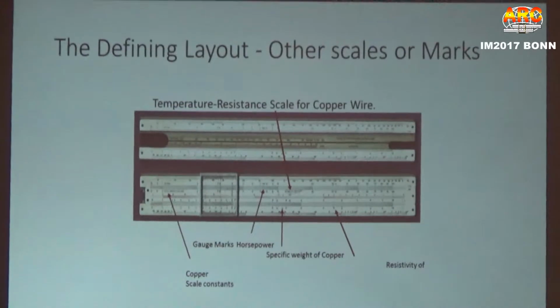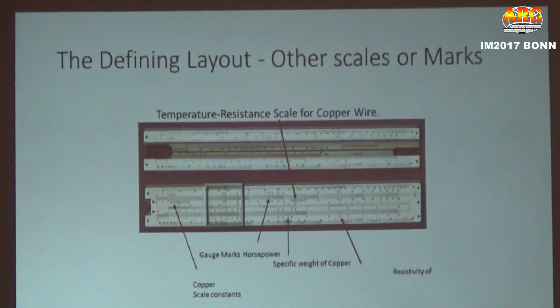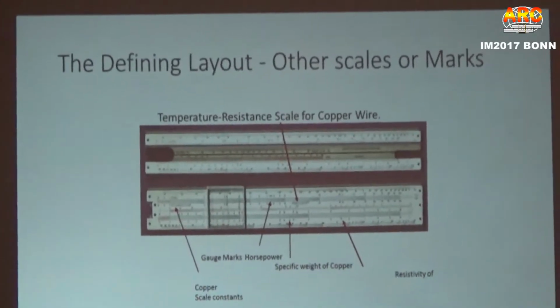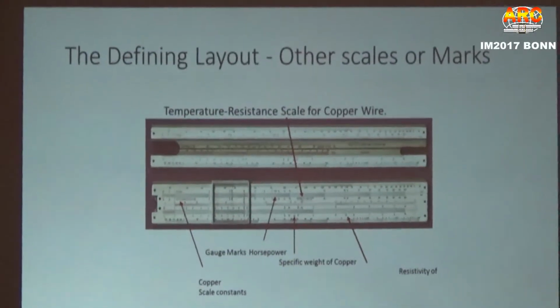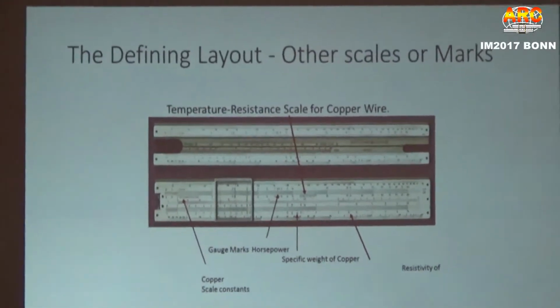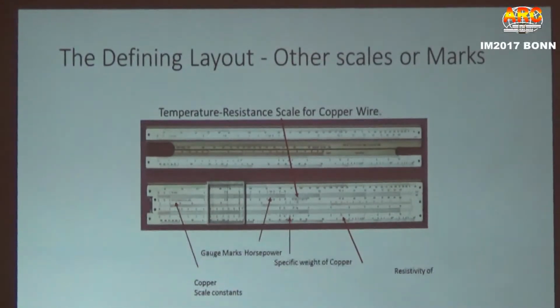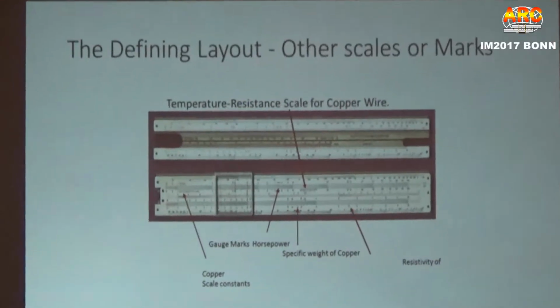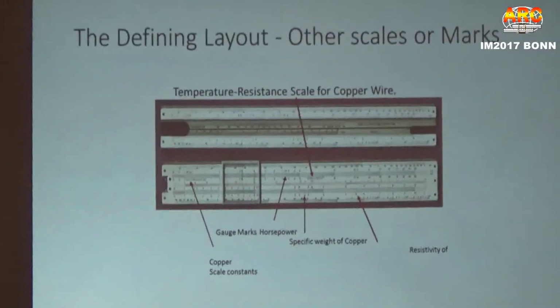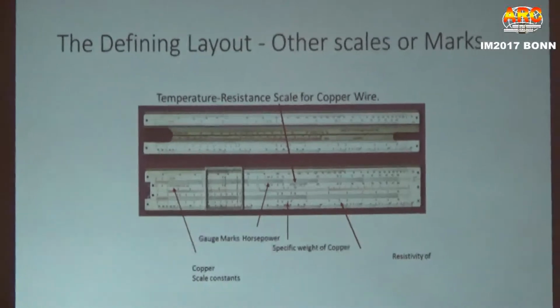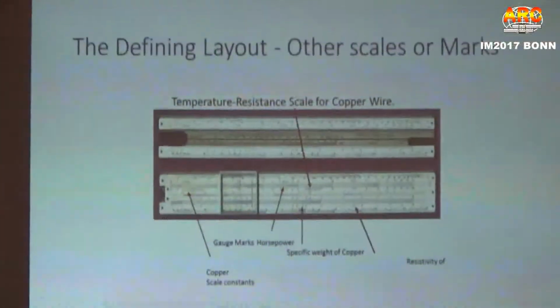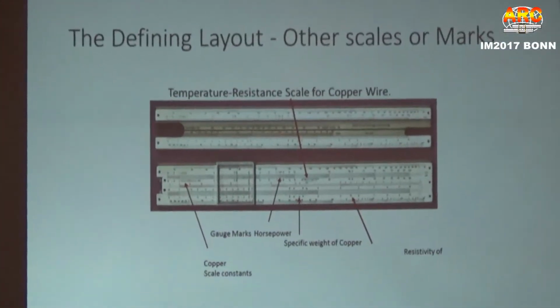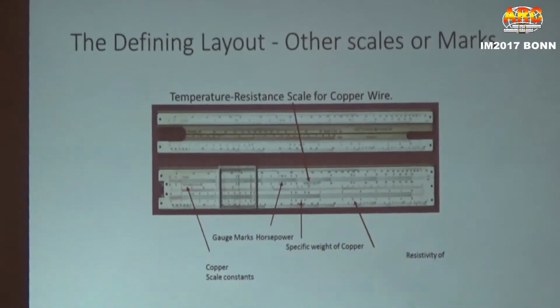Usually you're given a specific resistivity of copper conductor at 20 degrees C. So what you can do is actually work out the change in resistance of that copper conductor and use it in your calculations. For me in my job, 167 degrees or 75 degrees C wasn't quite enough. We actually run our conductors sometimes well up to 100 degrees C. So that's why you see steam coming off them every now and then.